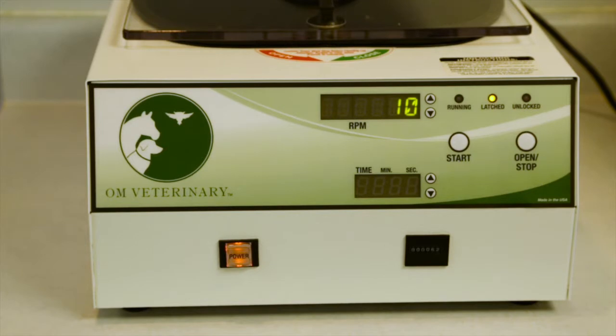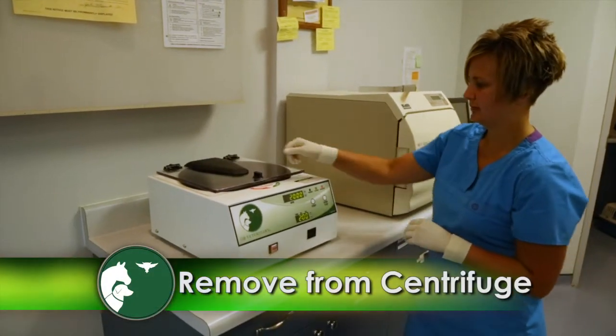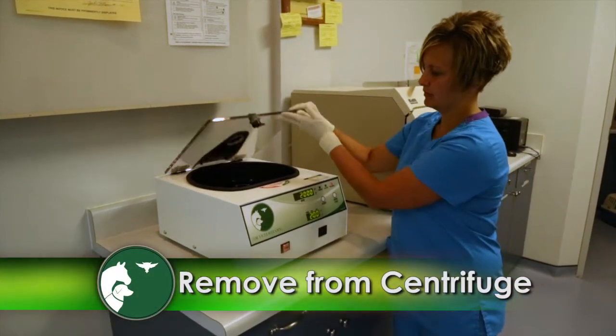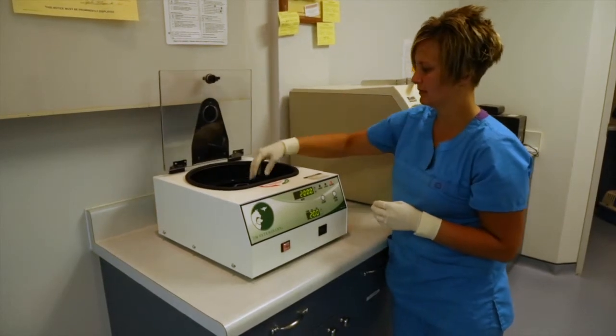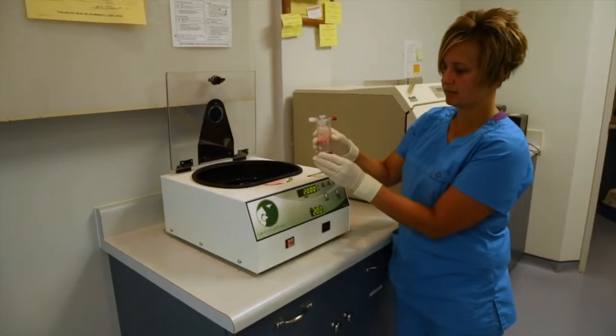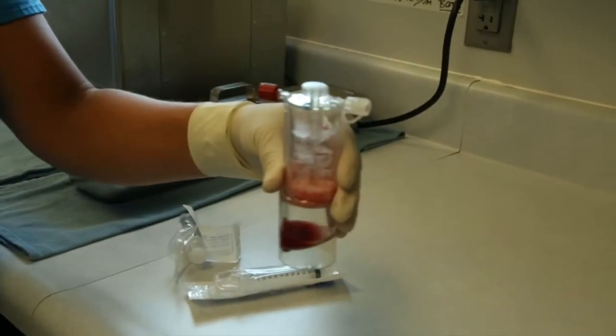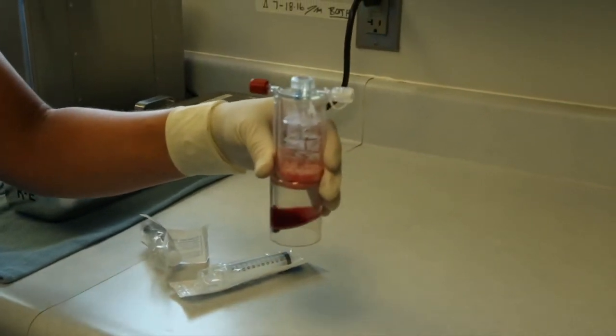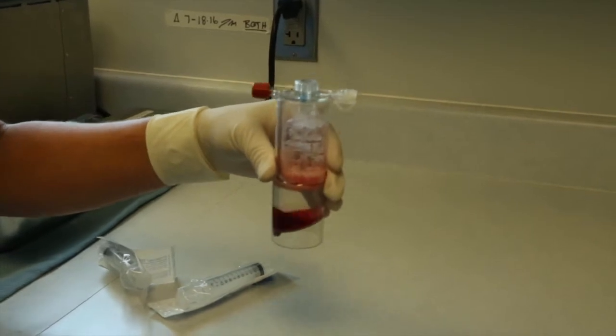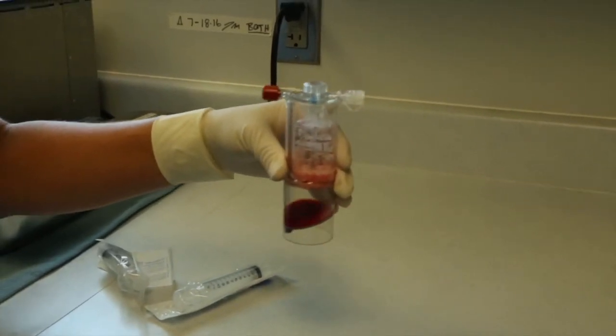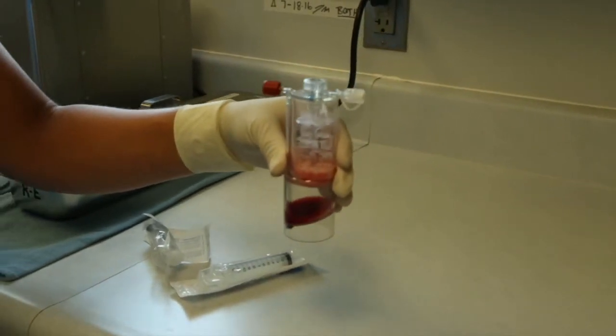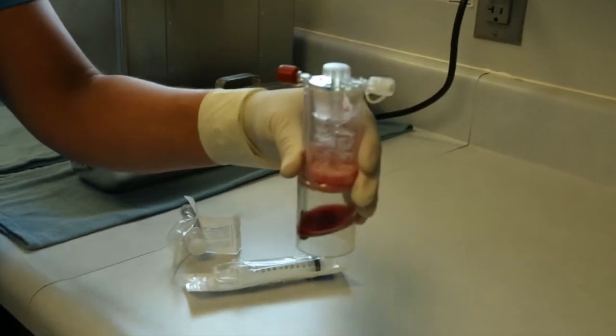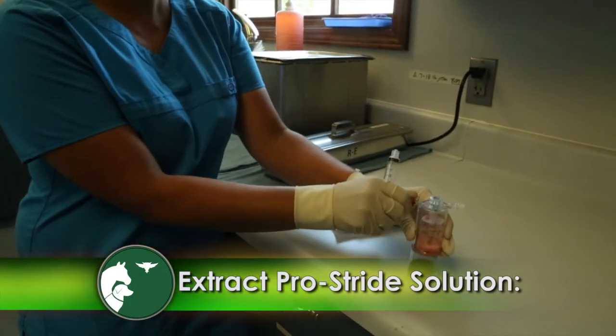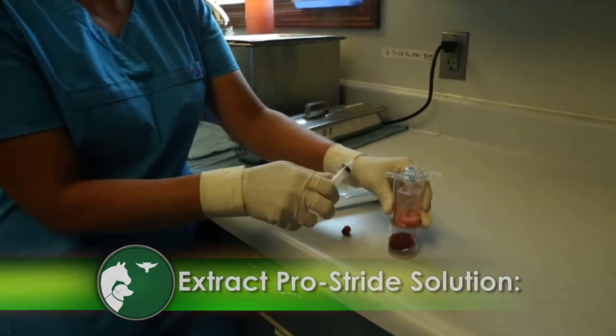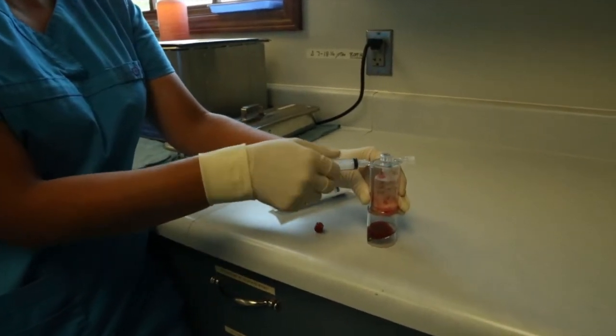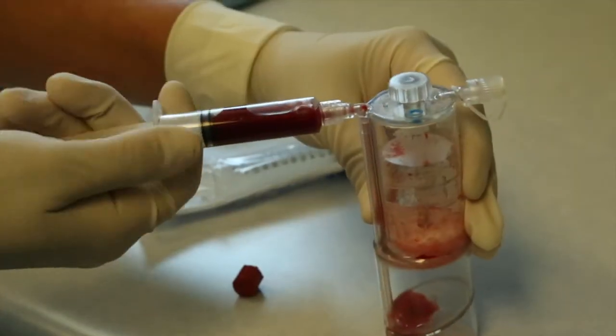At completion of the 2-minute spin, press the open button, open the top latch of the centrifuge, and remove the concentrator device. Prior to extraction from the concentrator device, gently shake before drawing into the final syringe. There will be a concentrated pellet of cells, so it is important to shake or agitate this concentration to allow for resuspension into the rest of the solution before drawing out for injection. Remove the red cap, number 2, and connect a 5 or 10 ml syringe you will use to inject. Extract the solution into the syringe, then disconnect from the device.